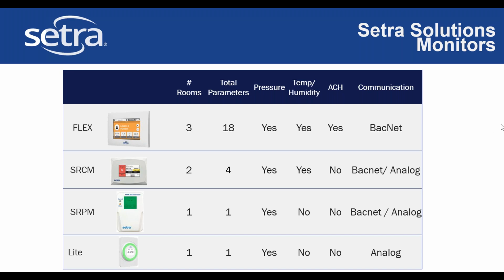From a regional perspective, what we have been coming across regarding the IVF labs is a requirement for pressure, humidity, temperature, air changes, and the quality of the air via particle counters. So usually this is what we see and come across in the region. And the short answer would be the Flex would be able to handle all of those parameters for you. The IVF lab generally looks, and I think we're talking about the room where they actually do IVF or the preparation space. The preparation space, though I do think they're pretty similar, the actual procedure room is often considered not an operating room, but not too far off. They're usually nearing that, which I think Rabia's note about what we see in the region speaks to.